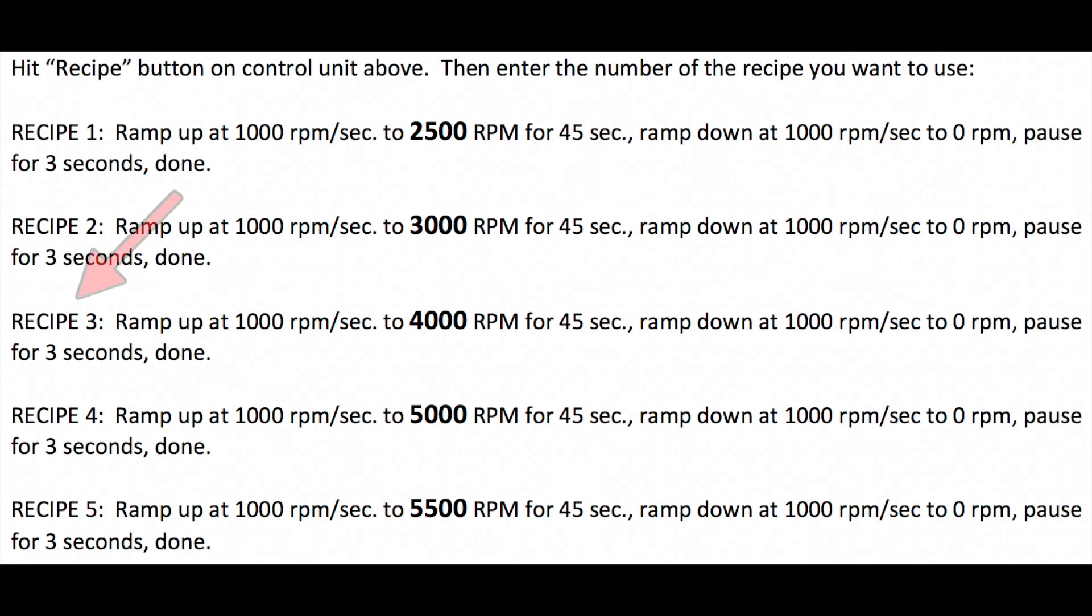For now, let's choose recipe three, which ramps up at a rate of 1000 RPM per second until it gets to 4000 RPM, and it holds at 4000 RPM for 45 seconds. Then it ramps down at the same 1000 RPM per second rate until zero. It maintains vacuum for an additional three seconds, then it's done.